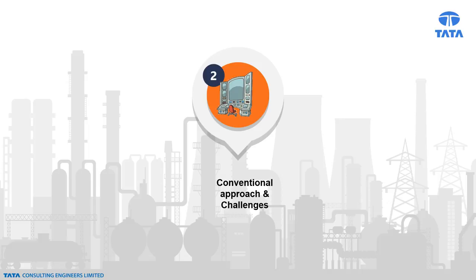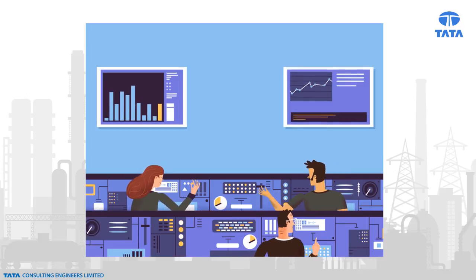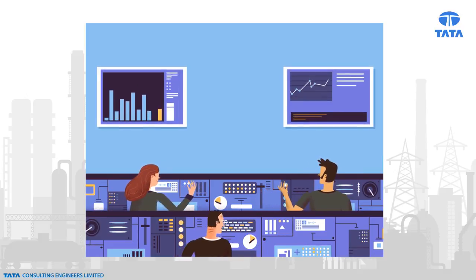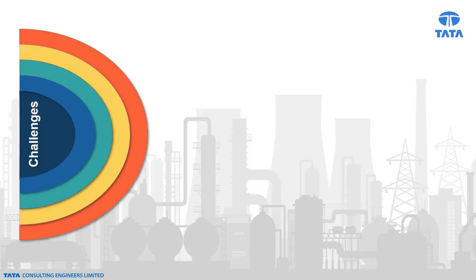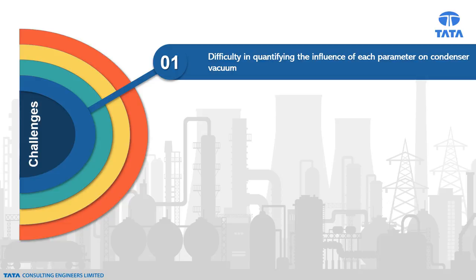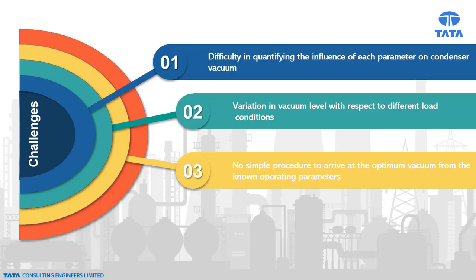Now let's look at the conventional management of the condenser and the challenges in this approach. Power plant operators aim to achieve optimum condenser pressure to get maximum efficiency for the plant. Currently, they face the following technical challenges: difficulty in quantifying the influence of each parameter on condenser vacuum, variation in vacuum level with respect to different load conditions, and no simple procedure to arrive at the optimum vacuum from the known operating parameters.